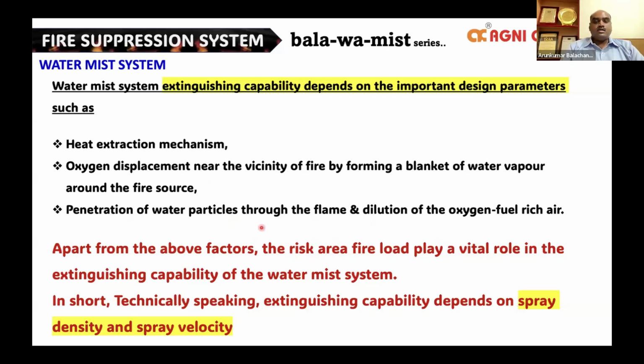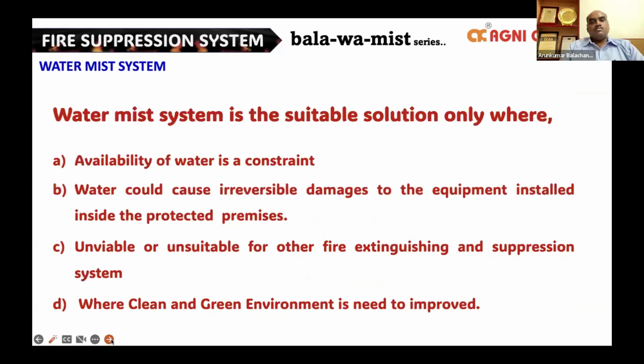And apart from this, of course, the risk area fire load will also play a major role in the extinguishing capability. In short, the extinguishing capability of a water mist system depends on spray density and spray velocity. The water mist system is most suitable where there is a constraint in the water availability, and water when used could do more damage than the protection of fire, where the other extinguishing agents are unsuitable or unavailable, and where a clean and green environment is needed, because water mist is a green system.